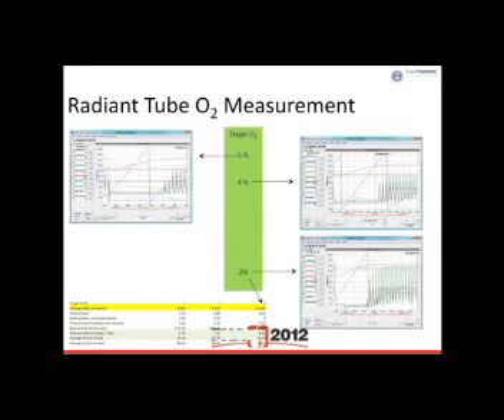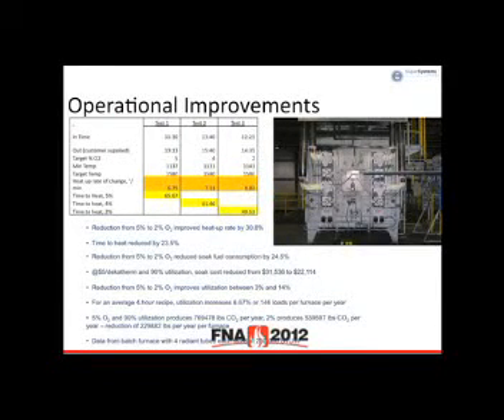If you look here, this is a case study. This is a chart where a furnace goes on high fire. You're looking at the O2 as a percentage in the exhaust gas, and the benefits are tremendous. You can look at your heat-up rates. When you're just looking at the products of combustion, at 5% oxygen in your exhaust gas versus 2%, your time to heat on these same examples went from 65 minutes to 49. That's 15 minutes per load. You start looking at how many loads do I run a year? How many shifts do I have? That's real money. As a byproduct of that, you're also getting gas savings.